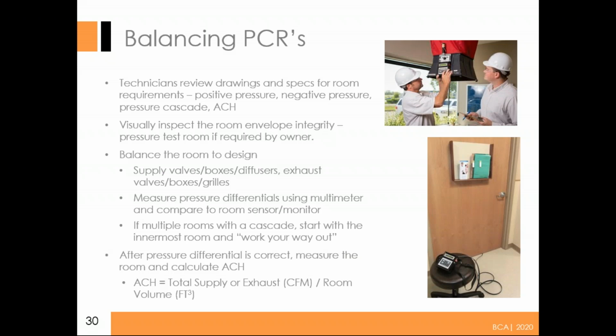One thing on this first page, on page 30, there is an error down there on air change per hour. It should be the total supply or exhaust times 60 divided by your cubic feet, your room cubic feet, to come up with your air changes per hour. In multiple room cascades, test and balance can really get tricky, like hospital rooms where you have your central sterile, which is typically in the center, which is going to sort of cascade out in different things. Clean rooms, your most inner space is your most critical to start with, and work your way out from there. You're going to be going back and forth several different times in adjustments. You make an adjustment in one room, how it affects the pressure and cascade of another room. I mean, it can get pretty back and forth.